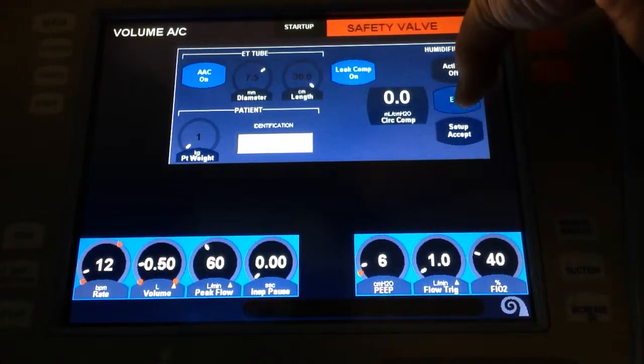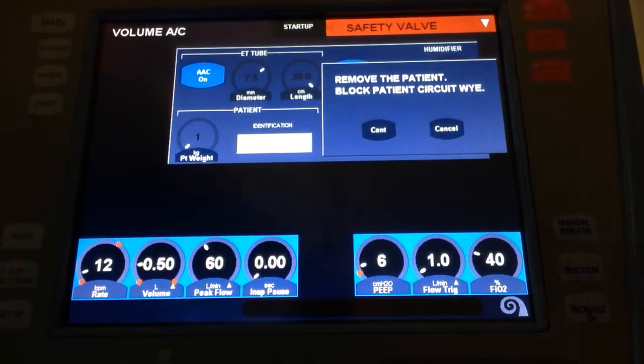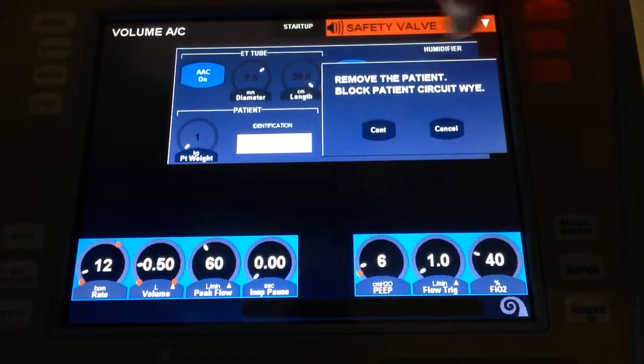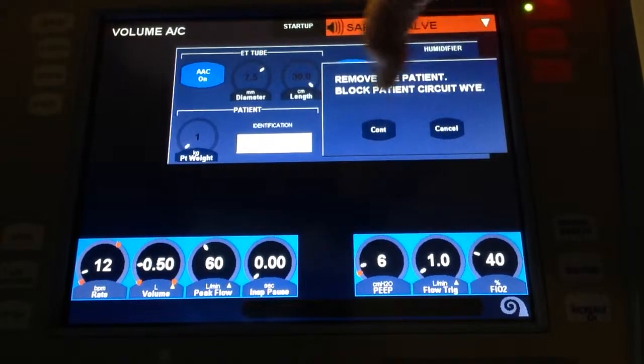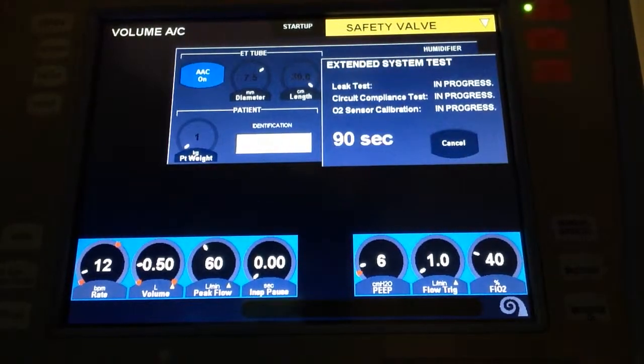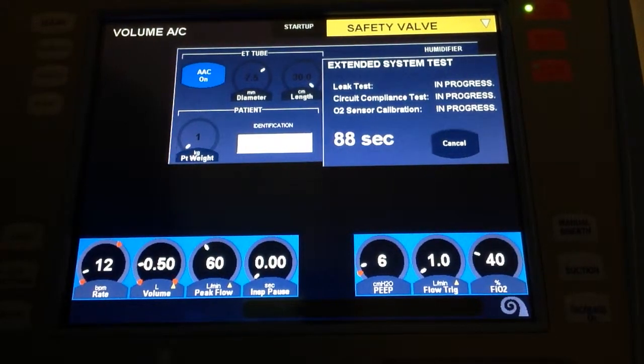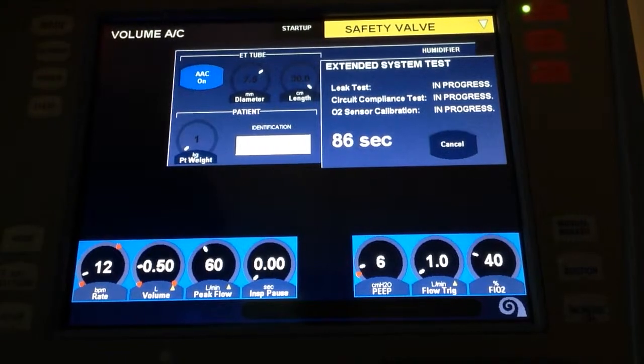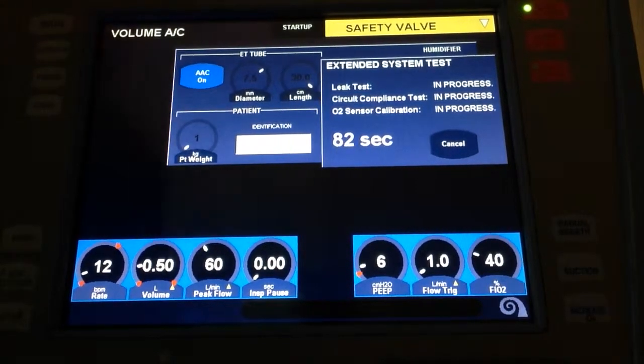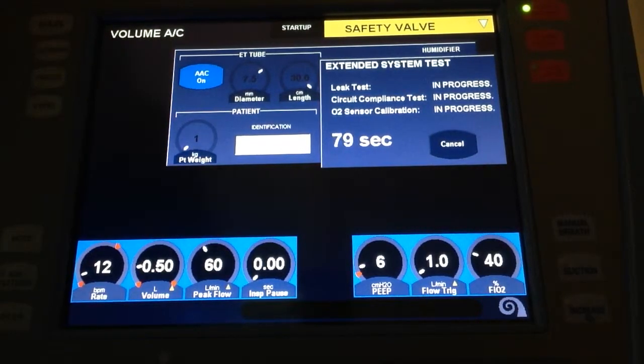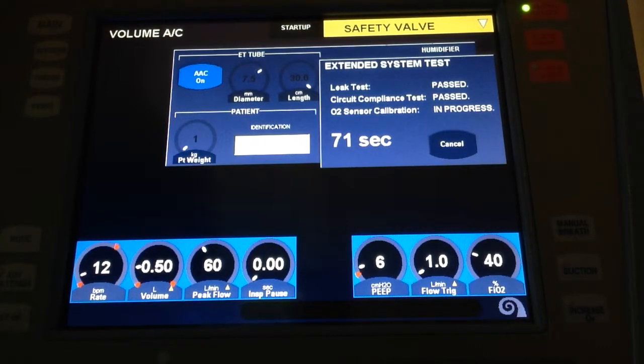So we're going to now start our EST. Remove patient and block circuit Y. I've done that, and I'm going to hit continue. Now, as you can see, it says leak test in progress, circuit compliance in progress, O2 calibration in progress. It's going to perform all three of these tests at the same time, or one after the other. So we've already passed two. It'll do this in a maximum of 90 seconds.